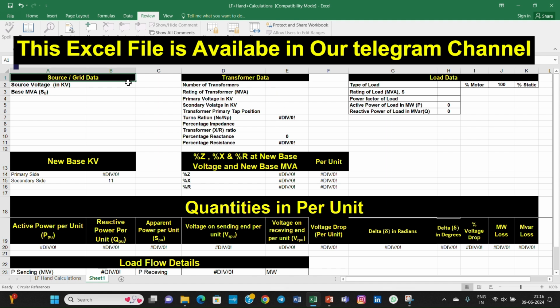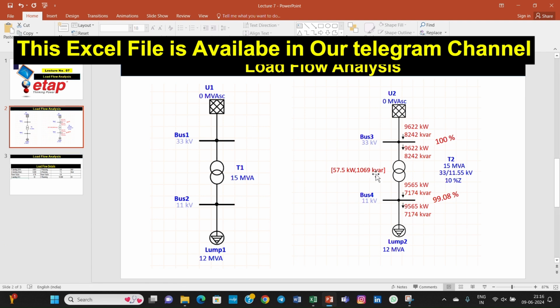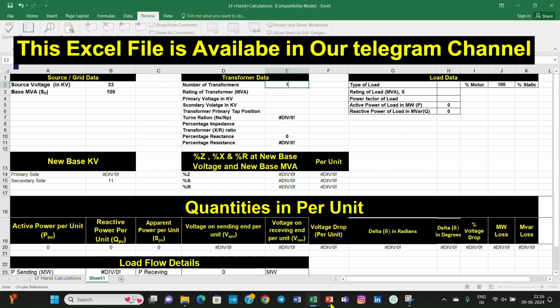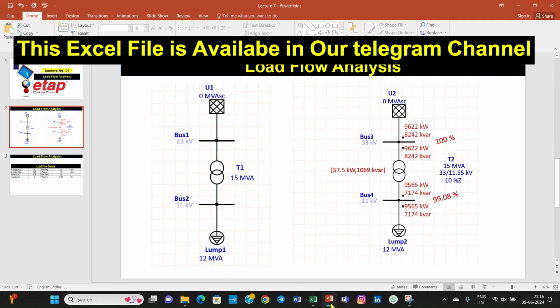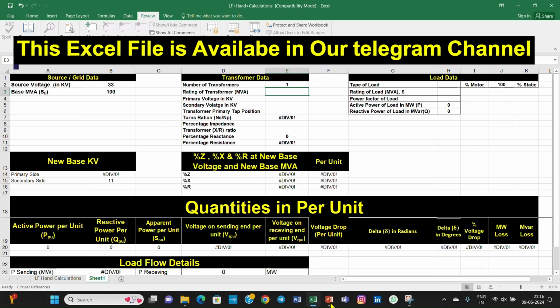First of all, I will enter the grid source. The grid is 33 kV, and the base MVA. The base MVA in ETAP is by default 100. Then we have the number of transformers in our electrical system. This is the system. The number of transformers is 1, so we can enter 1 here. Transformer rating is 15 MVA.